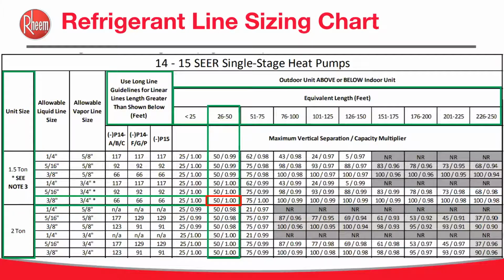So the thing to remember is line sizing charts for heat pumps and ACs are relatively the same. Every model and size of unit has its own line sizing charts, so it is imperative to follow the proper manufacturer line sizing chart. Remember, when charging a system with a TXV or EEV, the final charging is calculated by subcooling, and with a piston coil, it is done by superheat. But also, our systems are all matched with TXVs, so must be charged based on subcooling.